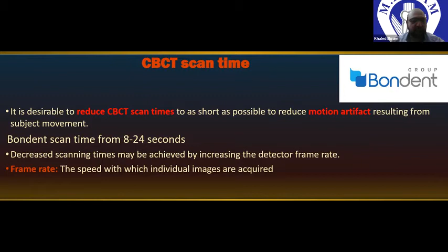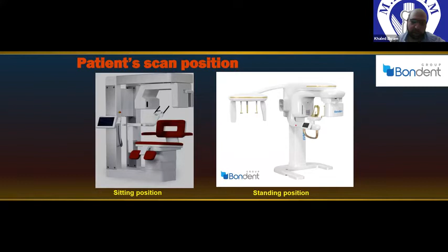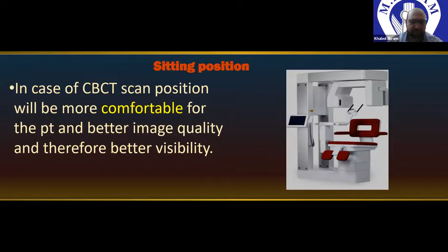The patient scan position. We have two types of machines. First is the sitting position. Second is the standing position. And in the old past, the first machine that was generated in the market was like a gantry bed, but I think nowadays it is not available anymore. So what is the benefit of having a sitting position machine? The benefit here is that this type of machine is more comfortable for the patient, so less possibility of having the motion artifacts. Although the standing position machine is prepared so that we can use a wheelchair or any chair to position the patient during the scan time, so we can get rid of this problem.